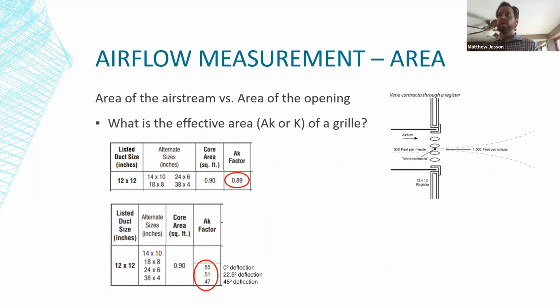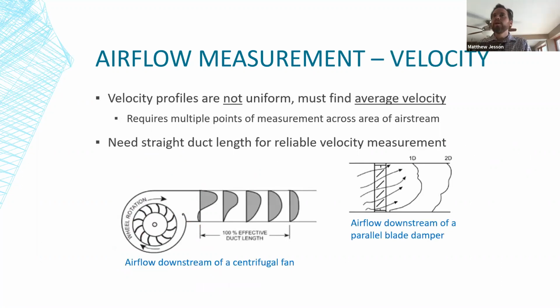It's not exactly stamped on the front of it or anything. So there's always some guesswork to a degree involved in that, and some judgment required. The second part of the equation, velocity, is more complicated, really, because velocity profiles are not uniform. You have to find an average velocity for the airstream, which requires multiple points of measurement across its area. So if you're doing a duct traverse, you need to have some straight duct length.